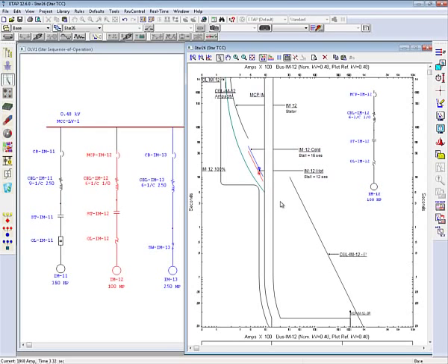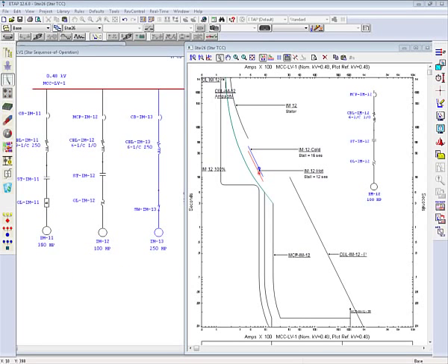Another important tool which helped me here to correctly view my one line star view is the combination of these protective devices' curves. So if you have two protective devices in series, you can combine them together to get an accurate curvature of protection of this motor. We can also notice that the cable damage curve is protected as it's not intersected by the MCP.